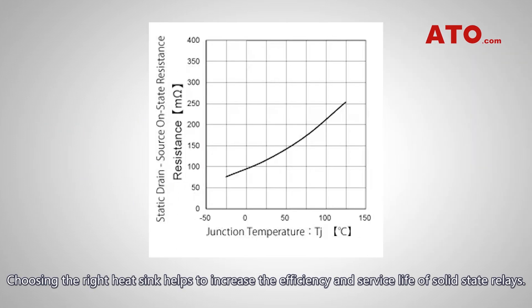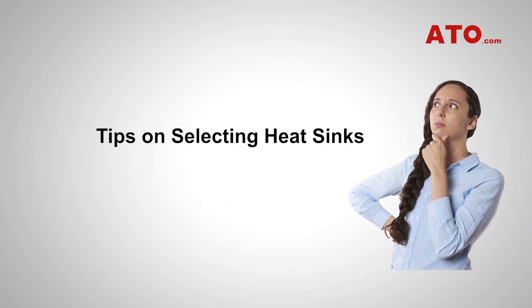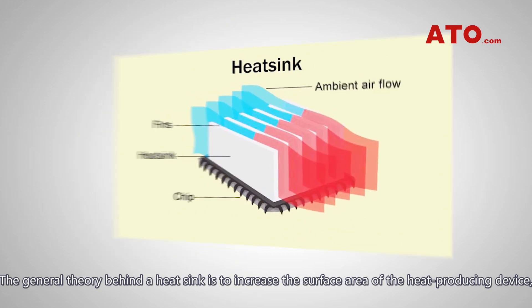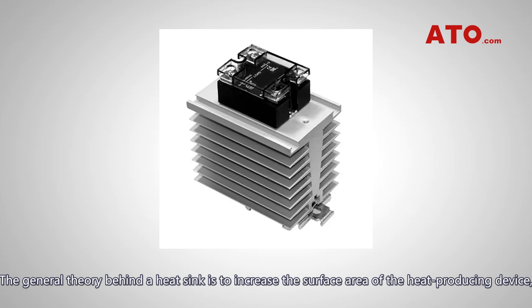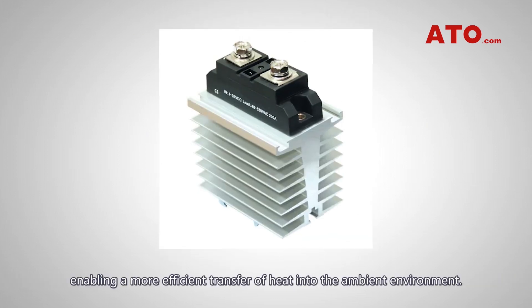Choosing the right heat sink helps to increase the efficiency and service life of solid-state relays. This video is intended to give you more insights into the selection of heat sinks. The general theory behind a heat sink is to increase the surface area of the heat-producing device, enabling a more efficient transfer of heat into the ambient environment.